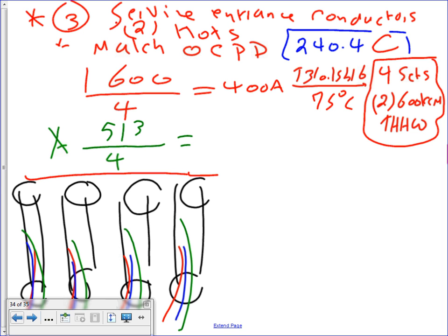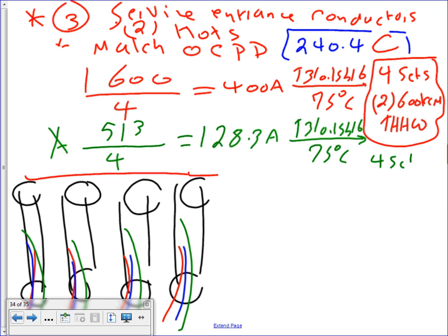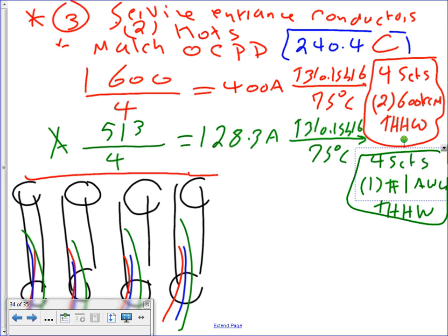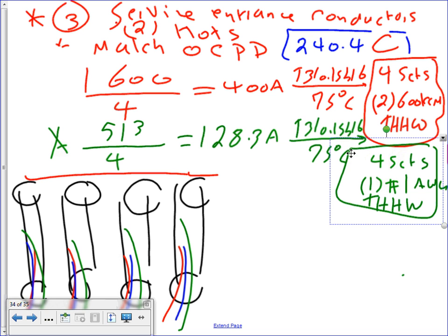Okay, when you do your math on this one, guys, you're gonna end up with 128.3 amps. If you take the math to table 310.15(B)(16) under the 75-degree column, same as we did with that one, you're going to end up with the same thing, 4 sets, exactly. One conductor, number 1 AWG THHW. Any comments, guys? Any questions? Any comments? Any questions? Any comments? Any questions? Oops.